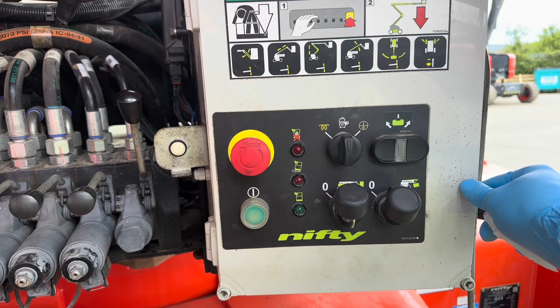All right, let's do the first thing now, which is check the resistance on the Canbus line. This is terminal 9 and 8, your CAN high and CAN low, and these two wires are coming from the cage. So I'll measure resistance on them and see what we have. We should have 60 ohms, so I would expect to see that. Let me get the multimeter into resistance mode.